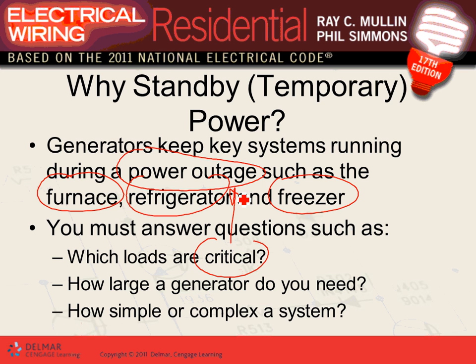How large would the generator be? Why can't I put the whole house on a generator, guys? If you put your whole house on a generator, your generator is going to be bigger. That's all. Can you? Yes. How simple or complex would the system be? If you want to back up the whole house, you're looking at 10 kW generators. They're expensive. A lot of people, guys, have 5 kW generators, and they back up certain parts of their building. 7.5 kW generator.